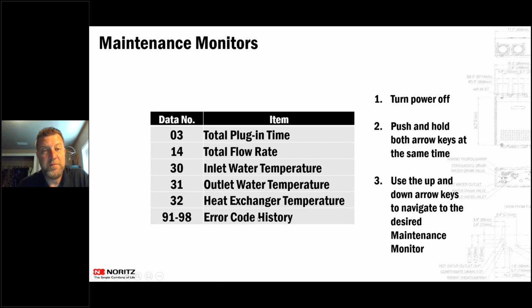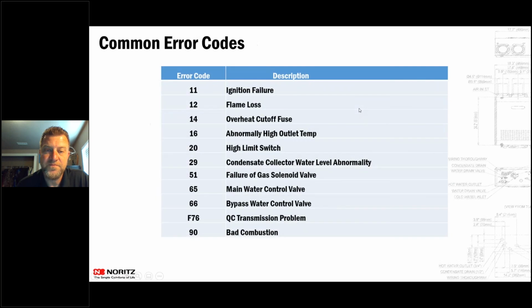There's a ton of different maintenance monitors in there. If it is flashing error codes, 91 through 98 are going to show you the last 9 error codes that it flashed. So you can see exactly what's going on with those units. Those error codes are very specific to different things inside of our units.